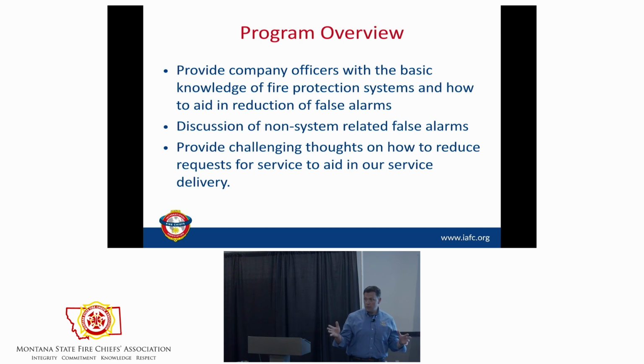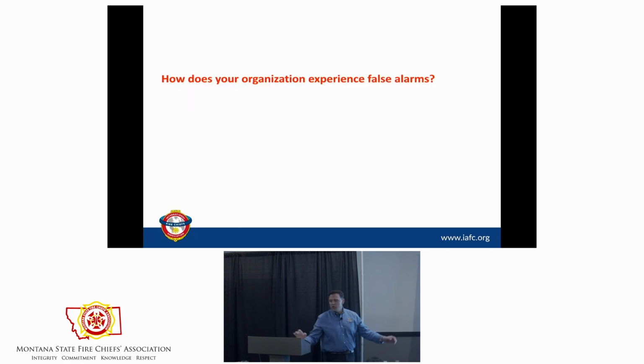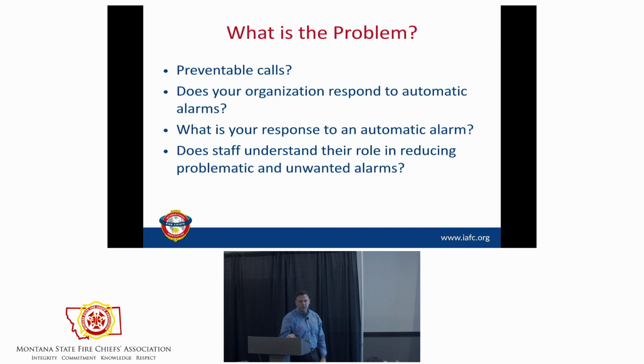Fire pump running is a good thing to monitor for because it shouldn't just run. But that loss of power is what was triggering a building alarm. And right, it was something that if we could have nailed it down sooner, we probably would have solved it. So if our responding crews would have read the fire alarm control panel and saw what it said, which is what? Fire pump loss of power, and put that in their reports, do you know how many bills and invoices we could have solved? Because we could have focused to that very specific issue. So really, we want to go through this and say, hey, look, there's this preventable call that we can prevent collectively. It's not a prevention thing.